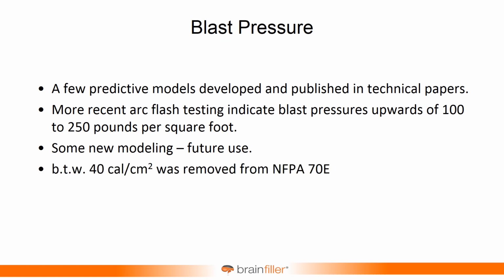By the way, with this blast pressure thing and it blasting you into the wall and the bug splat comment that I made, the 40 calorie per square centimeter note that was in NFPA 70E, that's what set off a lot of that. It was something that was brought in the 2000 edition. And over the years, people began to recognize, well, it's not so much a function of calories per square centimeter incident energy as it is about short circuit current. So the latest edition of NFPA 70E just simply removed it, and with really good reason. What they did is they stated, what's 40 calories have to do with de-energizing? That's what this was about. Above 40 calories, there should be a big emphasis on de-energizing. And the rationale was, what's 40 calories have to do with this? You should always de-energize. So that was a genius move to handle it that way.